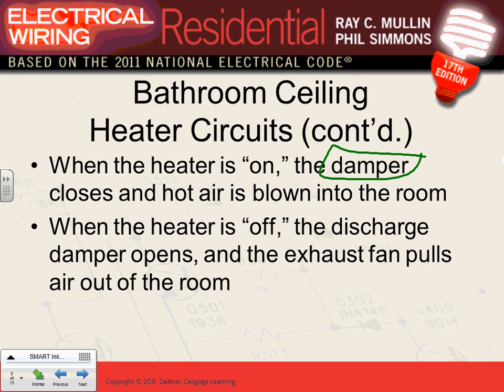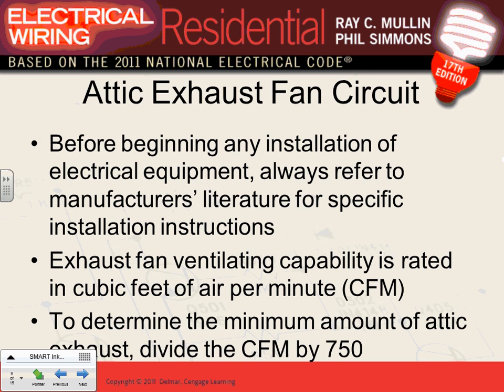The rest are a piece of cake. The night light just turns on and off by itself. The regular light is on and off by itself. Can I have thumbs up, guys? We know how it works. The only difference is the damper. The damper opens only if you have the exhaust fan on by itself, because you want to exhaust the stuff out. If you put the heater on, the damper will not open by design. Everybody knows what a damper is, that one that opens a little to exhaust the air out, right? So the damper would not open. That's basically because you want to pull the air in or push the air out.